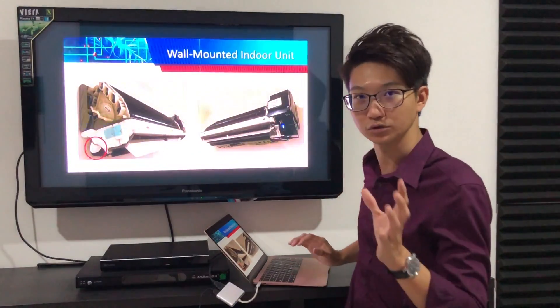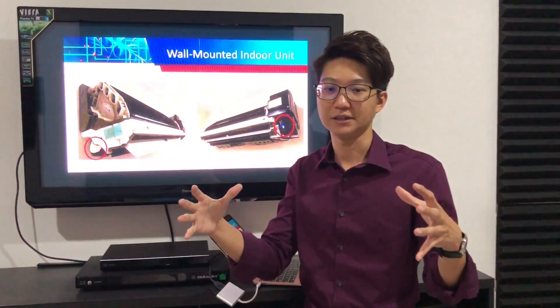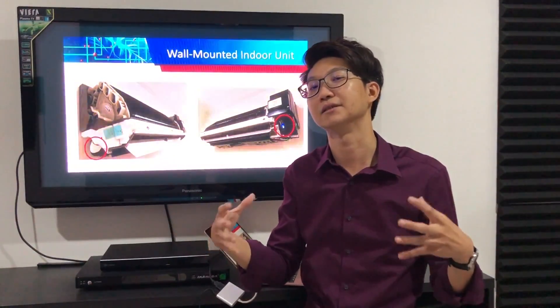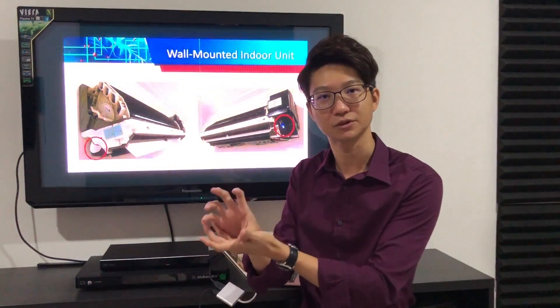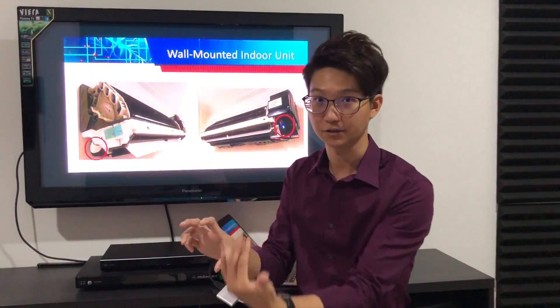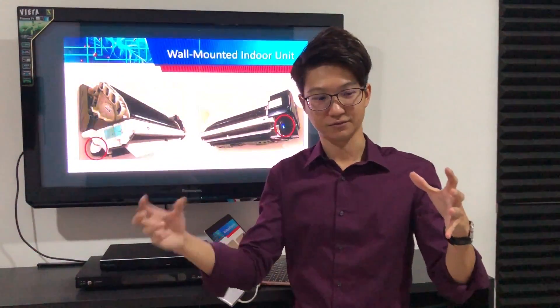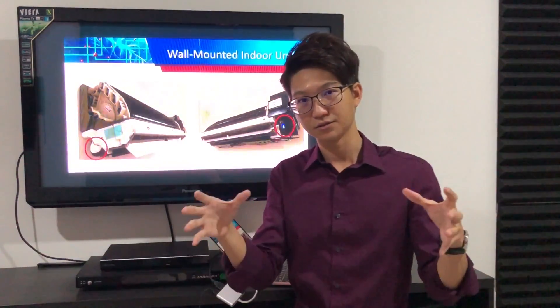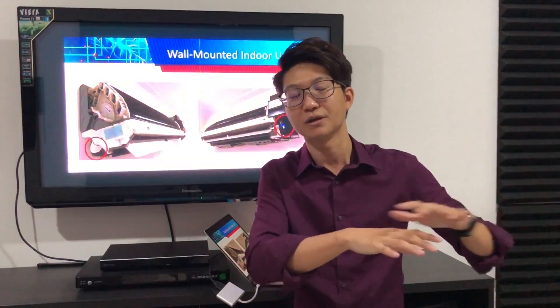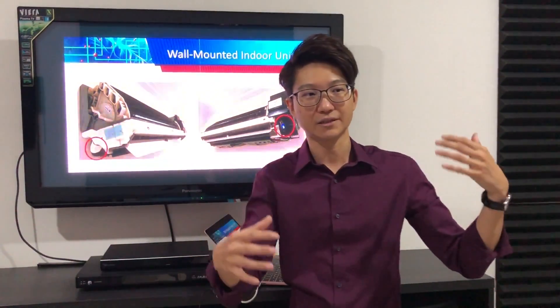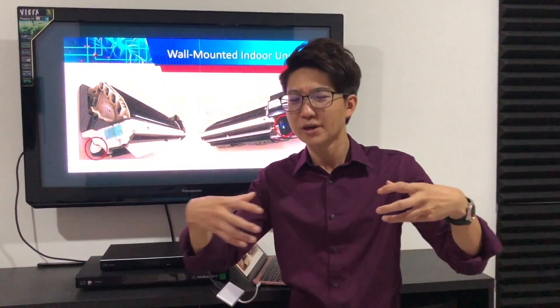Most indoor units have a temperature sensor — so basically the indoor unit acts as a thermostat. In the commercial sector, a separate thermostat is used to sense temperature and control the air conditioner, but now the indoor unit itself has a built-in temperature sensor. That's why the location of the indoor unit is very important. If you put it at the corner, not only is air distribution poor, but the temperature sensor won't read the actual average room temperature — causing insufficient or excessive cooling. Usually the indoor unit should be placed somewhere near the center of the room.